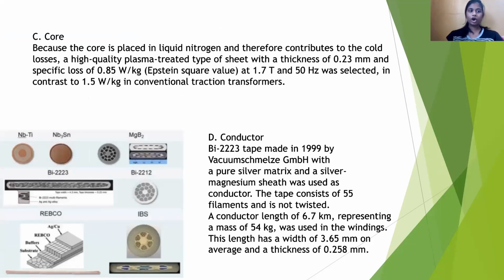Core. Because the core is placed in liquid nitrogen and therefore contributes to the cold losses, a high quality plasma-treated type of sheet with a thickness of 0.23 mm and a specific loss of 0.85 at 1.70 T and 50 Hz was selected, in contrast to 1.5 in conventional traction transformers.